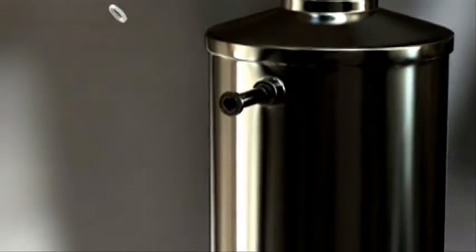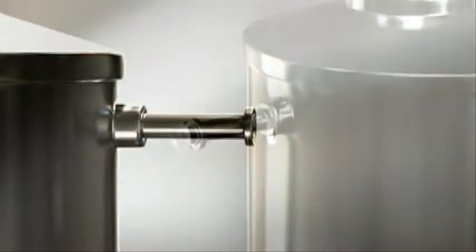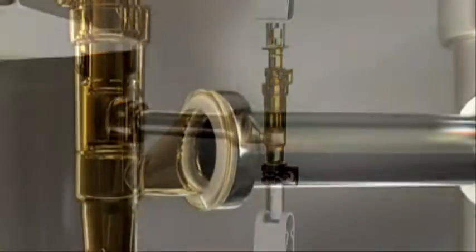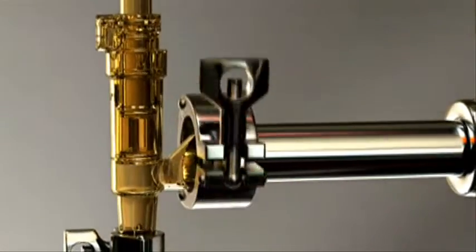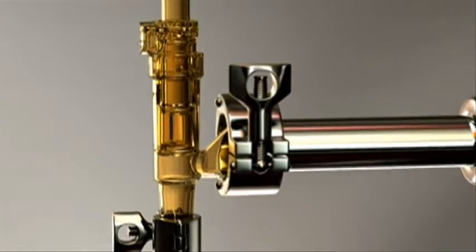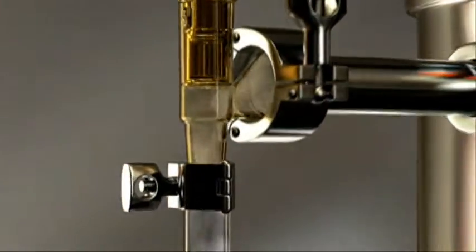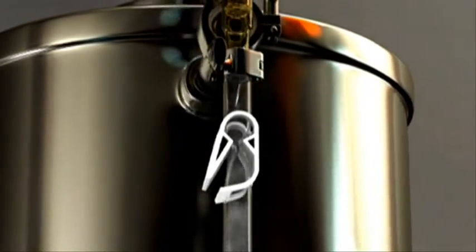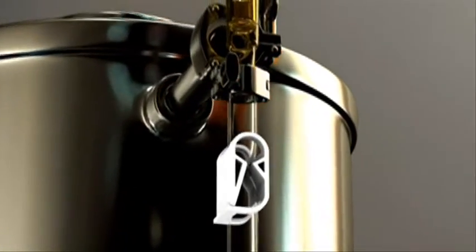The Steam-Through-Connection's three-port design allows for a quick and easy sterile connection. As seen here, the middle port is being connected to a bioreactor, with the lower port already connected to a steam trap. Steaming through the lower two ports creates a steam-on sterile connection without the time-consuming cleaning processes or validation concerns associated with reusable devices.